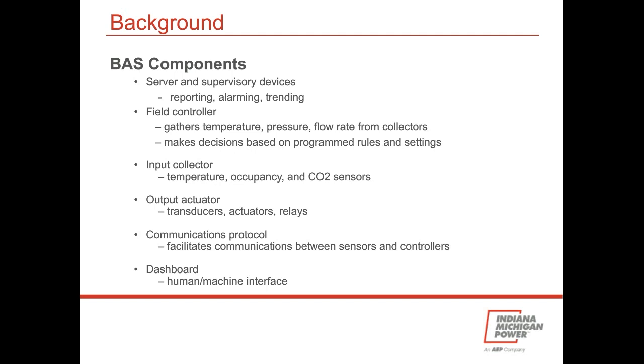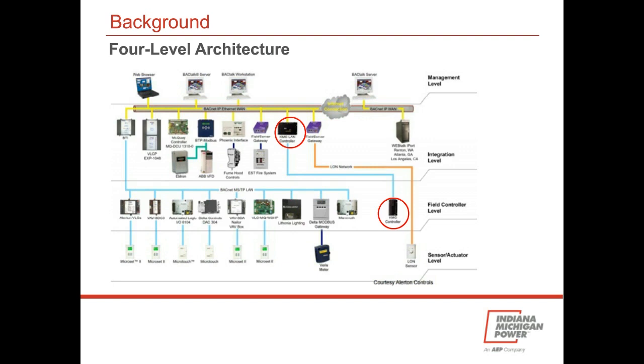Here's a picture, worth a thousand words. If you look at the very bottom and go upward, there's a 4-level architecture you'll typically run into. At the bottom, sensors and actuators measure temperature, airflow, pressure, even air quality like CO2 sensors, occupancy, and outdoor temperatures. Then you have field control level devices, which I've circled here -- we'll look at examples of those. They take that data, do some decision making, and pass some of it upward to the integration level, which we call supervisory controllers. Finally, there's the management level where the user interface is involved. All this has to be connected together over various wired and wireless communication means. It is complex, no doubt.